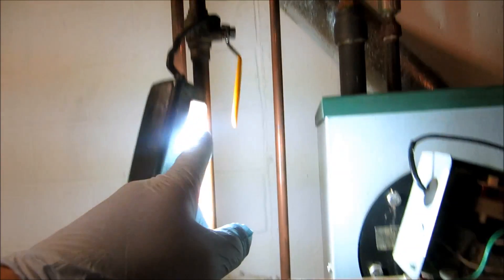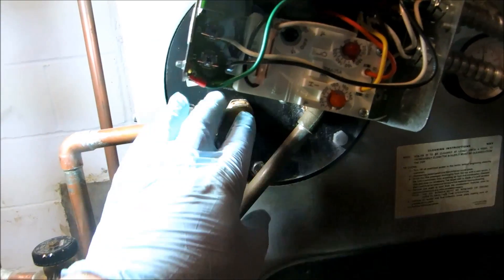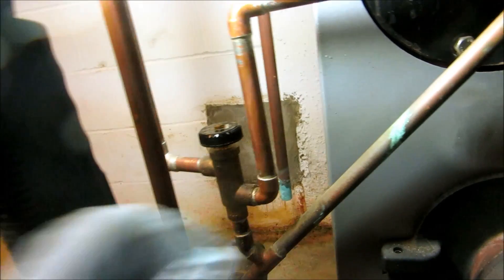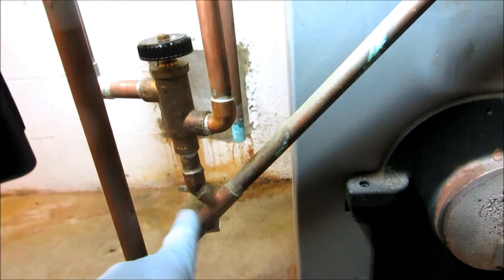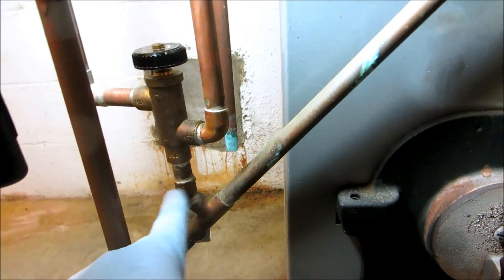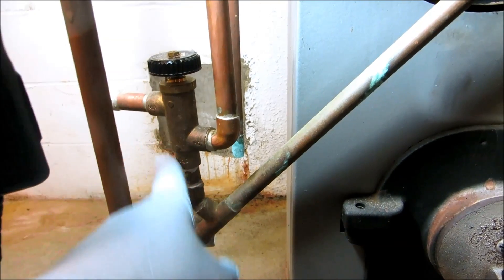Cold water comes in here from the ball valve, comes into the tankless, gets heated up, comes out hot to the tempering valve, then goes up to the fixtures. I'm gonna put a ball valve right here because the cold and the hot is being mixed here — the ball valve will be able to adjust this to give her continuous hot water upstairs for her shower.